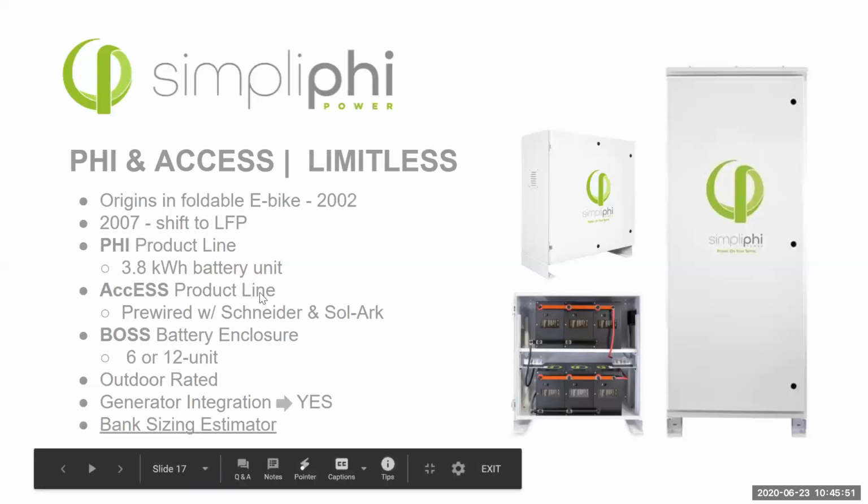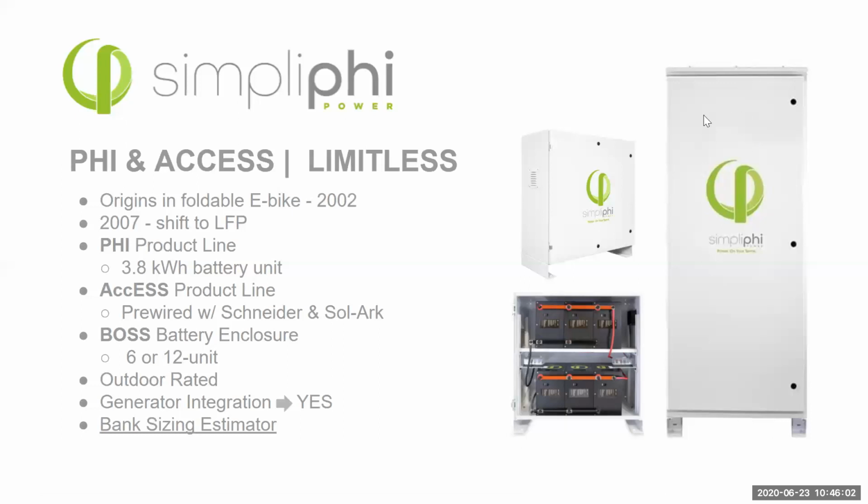The Access product line, if you open this up, is going to include batteries down below and a hybrid inverter up top. You can get them pre-wired with Schneider or with Sol-Ark. With Schneider, you can have them with or without the charge controller if you want an AC coupled or a DC coupled version. Sol-Ark is AC and DC coupled by nature, so there are no charge controllers you would need to worry about.